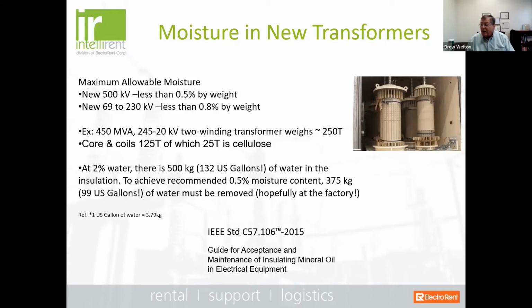Now, if we talk about brand new transformers, and this is kind of interesting, IEEE C57.106 is the guide for acceptance and maintenance of insulating mineral oil in electrical equipment. They say that for new transformers, for the smaller ones, 500 kV or less, we want to have about 0.5% by weight in terms of moisture content. As you get into the larger transformers, or I'm sorry, the smaller transformers are 0.8, the larger ones are 0.5.